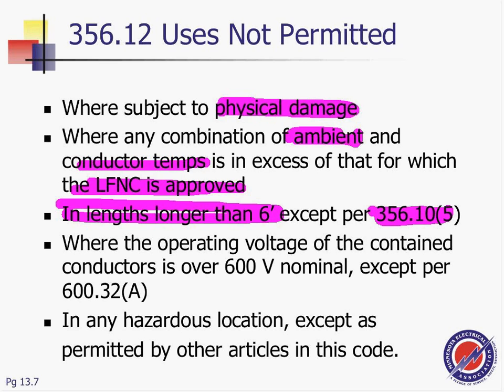There is a limitation on the voltage, and also an exception for that one for most cases. I mean, 600 volts is nothing to sneeze at, but this conduit is not meant for high voltage. It's also not for hazardous locations, and there are some exceptions where it is permitted in other articles. Generally speaking, you have the limitation of size, voltage, hazardous location, temperature, and physical damage. Any questions, guys? Anybody have any questions about this conduit of choice? Any questions?